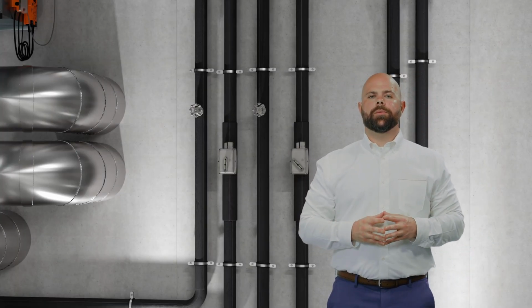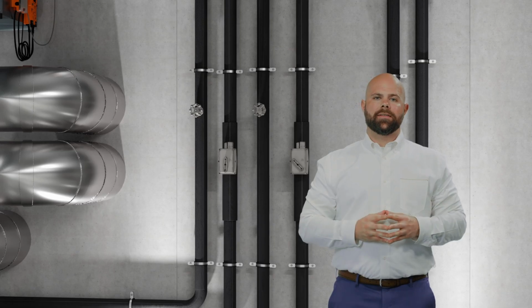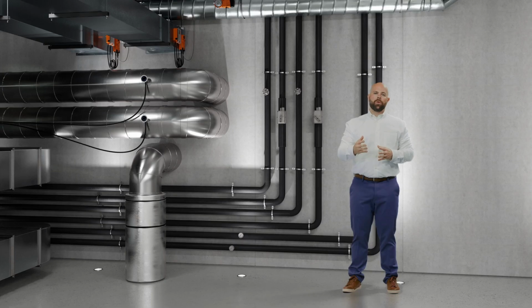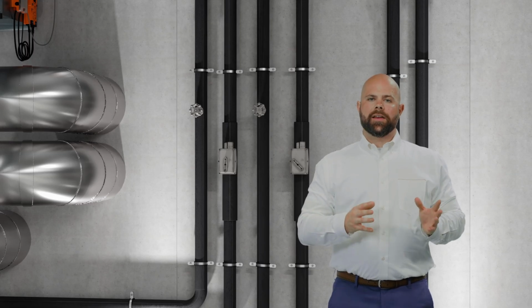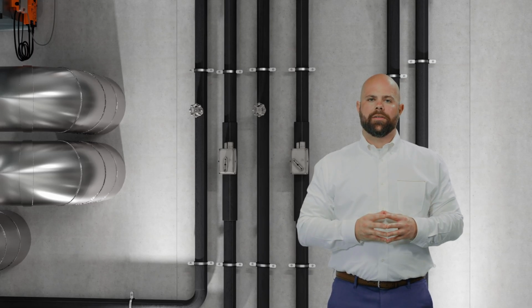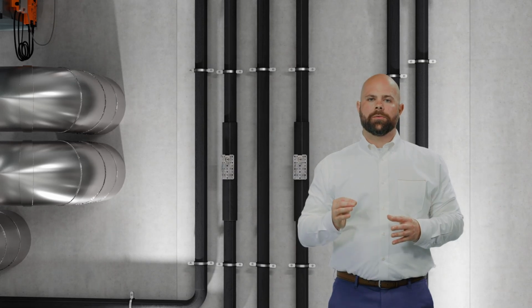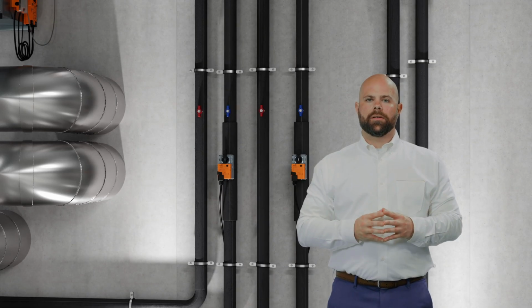Replace old with new. Maybe you have end devices in your building that just aren't working properly anymore. Maybe they're old, or maybe they're just manually controlled. In any of these cases, sometimes replacing them completely is the best next step. It doesn't even matter what type of actuator you currently have on your control valve, we always have a suitable replacement for the linkage, so you can replace the actuator with a modern standard.